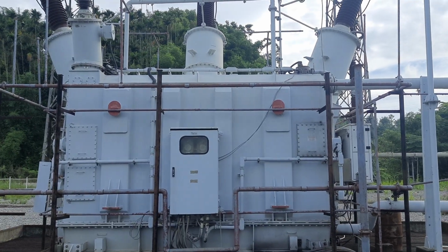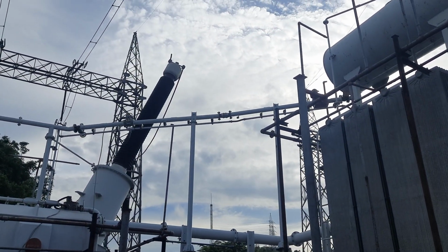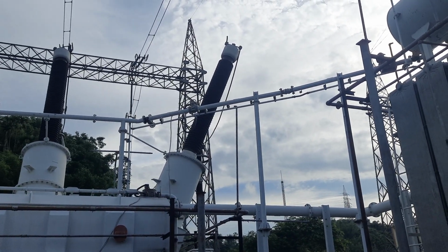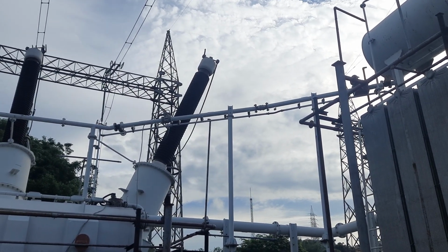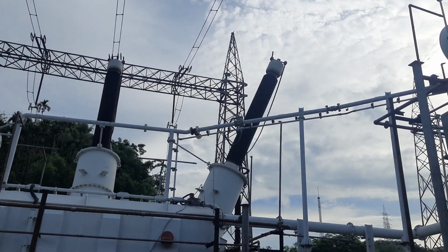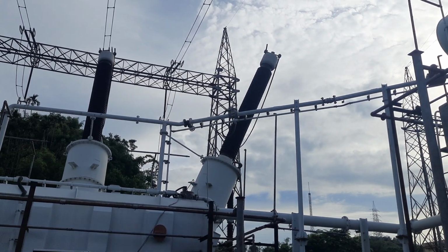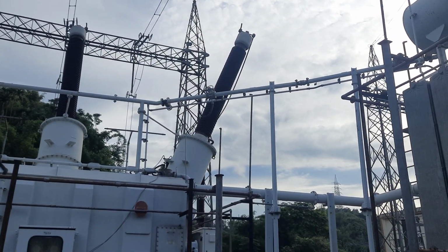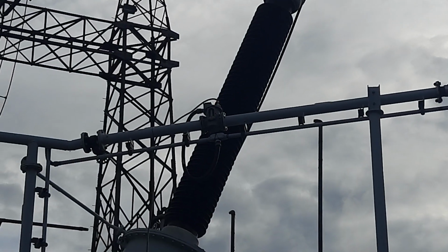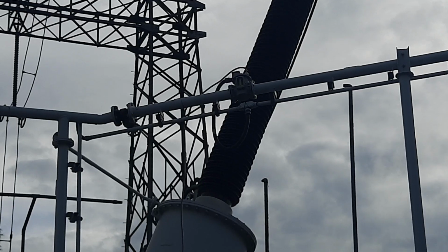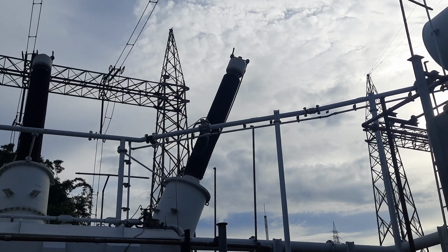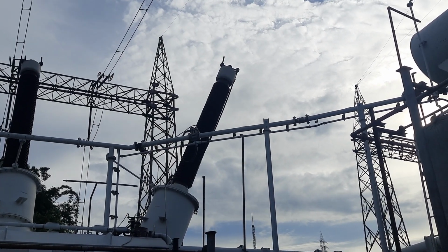And number two is that it is inclined at an angle of 1 to 5 degrees, I would say, towards the main tank. It is not actually installed horizontally, but it is made to incline at some angle so that the oil flow is facilitated. So this is the position of the Buchholz relay. It is quite important. In addition to your pressure release device or pressure release valve or your oil surge relay, we are installing one more device, that is a Buchholz relay. It is quite important in all power stations.